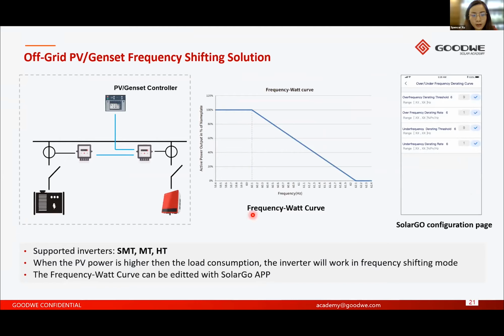In the off-grid applications, the main difference is that the system is not connected to the grid. So the genset and the PV inverter form an independent microgrid, and the genset actually plays the part of the grid. In this case, there's no export power to the grid. So the genset controller will control the PV power output through the frequency shifting function of the inverter. The inverter will measure the generated solar energy and the load consumption together. Once the PV power is higher than the load consumption, the frequency of the system will be adjusted, and then the inverter will start derating once it's over the frequency threshold. The frequency-watt curve can actually be edited through our SolarGo app, which is GoodWe's configuration tool.